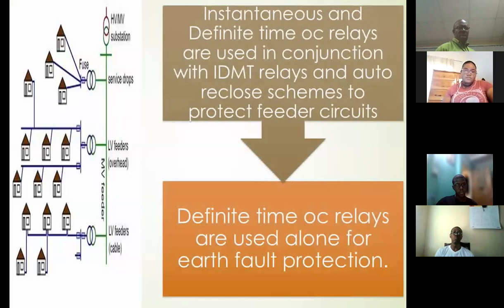In terms of the systems of protection, as I mentioned, the instantaneous and definite time are used with your IDMT and auto-reclose schemes for feeders.